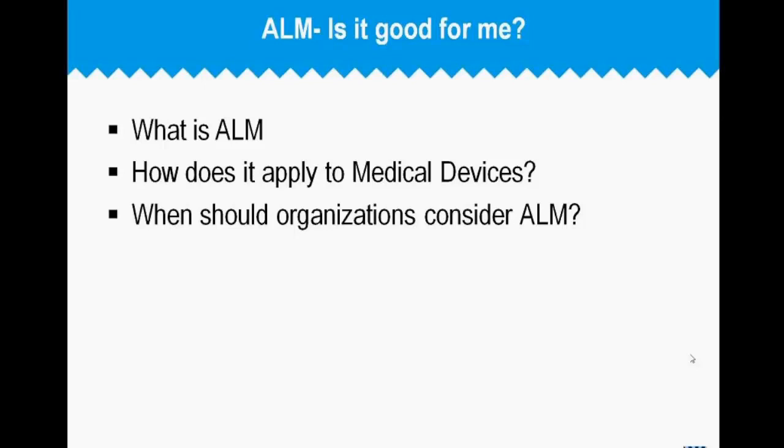I like the list you gave, Jamie. The one that I would add also is one thing that's kind of weird about medical devices compared to other industries is that we have to keep our design records around for like 17 years plus. So like a really, really long time. And if something very bad happens, all of those records will be pulled and gone through with a fine-tooth comb, and they need to be all accessible and be able to be understood and read.